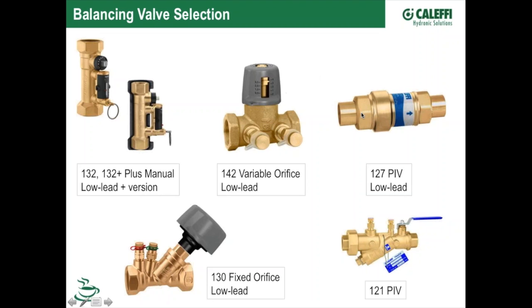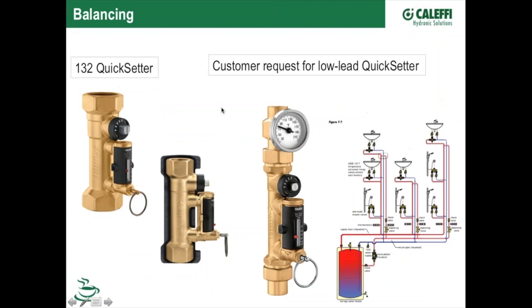This one here you buy, you tell us what you need for a flow rate. We'll build that and send it out to you, labeled. This one gives you the ability to change the cartridge in the field. We'll give you a tag that tells what's in there, how it was built. If you change the cartridge, it will come with a new tag. It does have the ports to confirm that you have the flow rate that you're expecting through that device. Pressure independent valve is what the PIV stands for. A little better shot of that Quick Setter Plus I was telling you about, and kind of an example where it might be used in a system. If I'm trying to balance multiple domestic hot water loops, I know that I need a certain flow rate to these different loops. I could use this valve and dial it in.